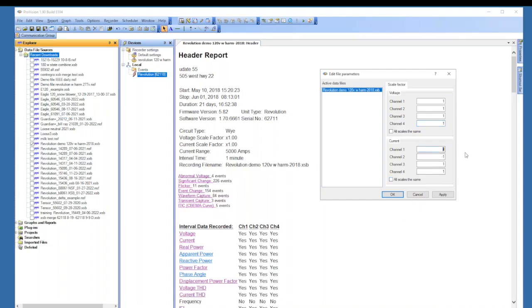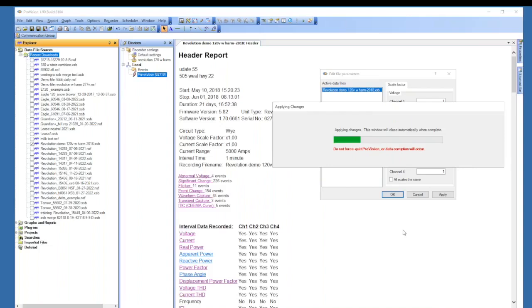If you double wrapped your Flex CTs, you need to tell someone who is working with the recording, and if it's double wrapped twice, then you would put a 0.5 in there. If you got it around 3 times, you can put a 0.33, and 4 times a 0.25. And then if it's on backwards, you can put a minus 0.5, something like that. And then when you click OK, you have to go in and double click again on that, and then you'll see those settings adjusted in there. So that was tools and scale factor.